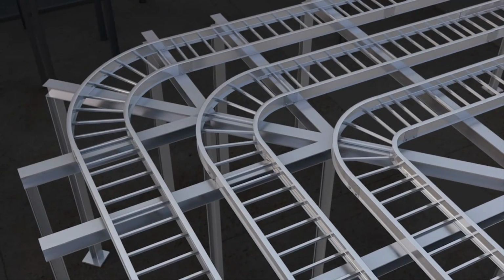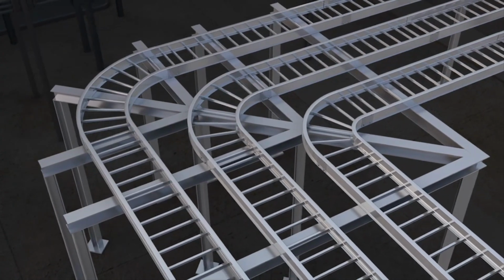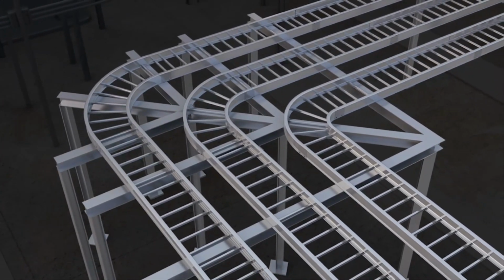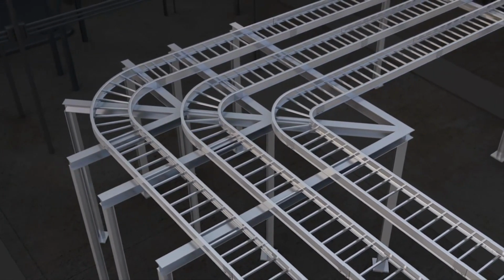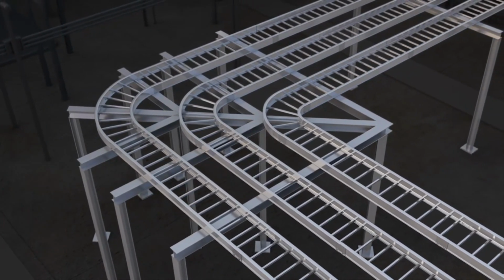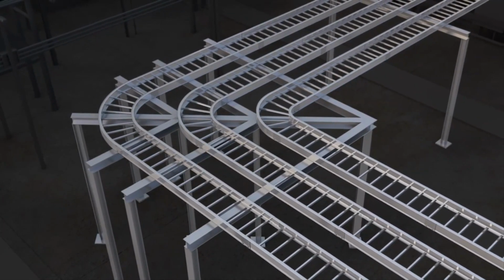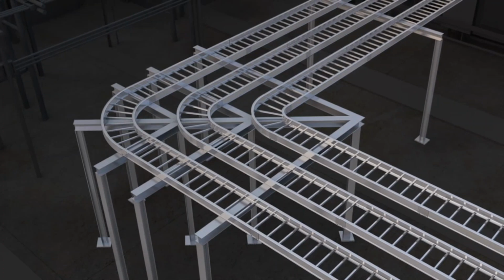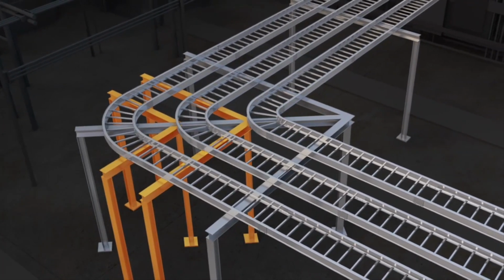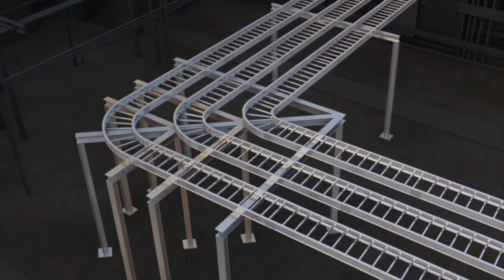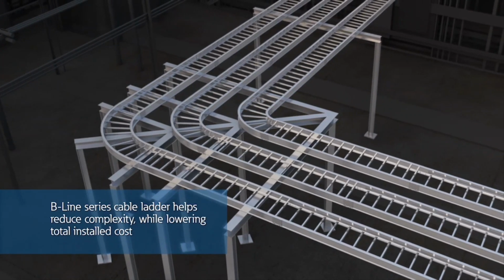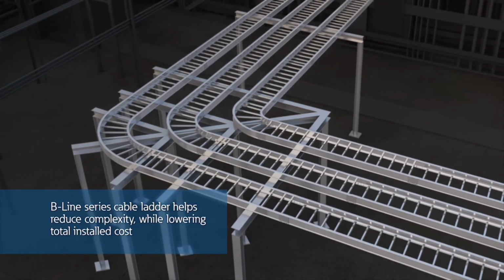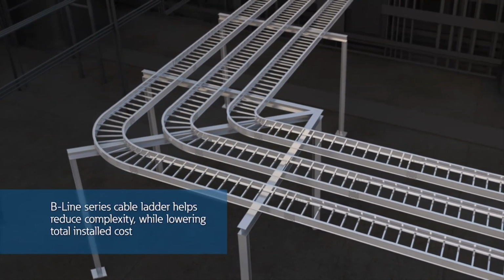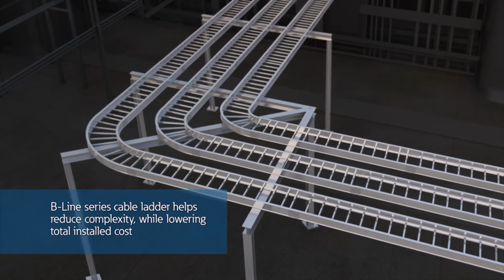In a typical industrial cable ladder application, multiple runs are utilized, which increases the support layout complexity. In this specific example, 3 runs of cable ladder make a 90-degree horizontal change in direction, requiring a minimum of 7 supports per NEMA VE2. Utilizing B-Line support recommendations, the number of supports can be reduced to 3, resulting in lower cost and lower installation complexity.